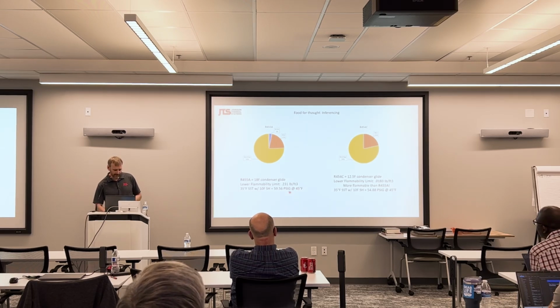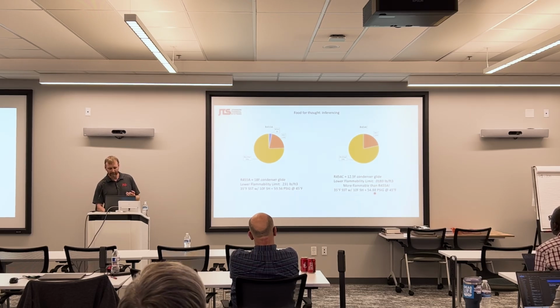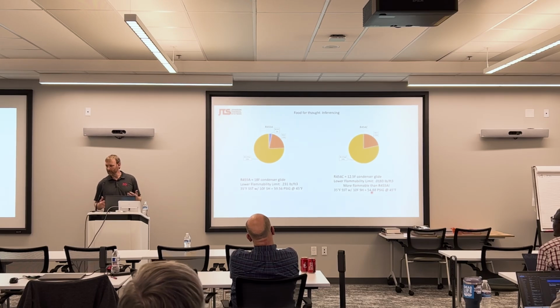Where I was getting at is basically your system, your suction pressure is going to end up operating at about 5 psi less if your 455A does convert into more like your 454C. But now your electronic expansion valve might not know that, right? So it's going to think that you have 13 degrees of superheat when you really only have 10. So it's going to start opening up if your set point's at 10, and ultimately you're going to end up operating the system with less than designed superheat.